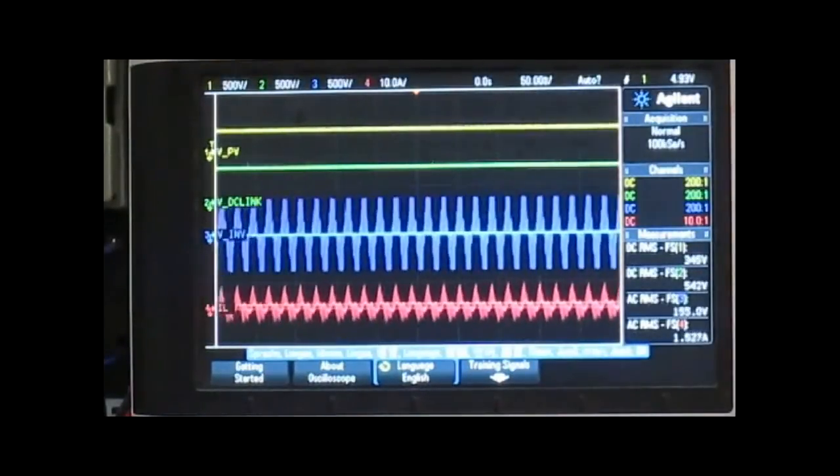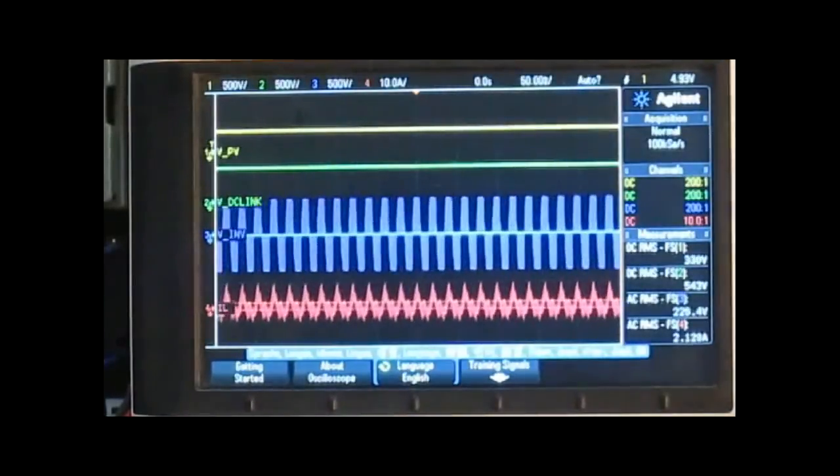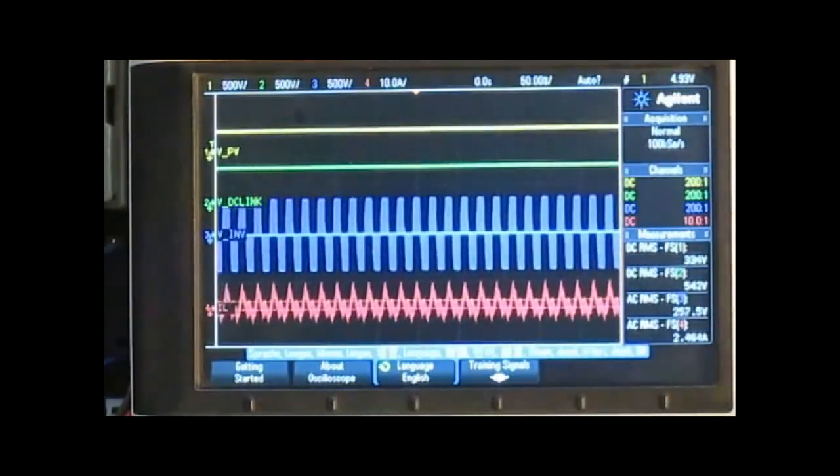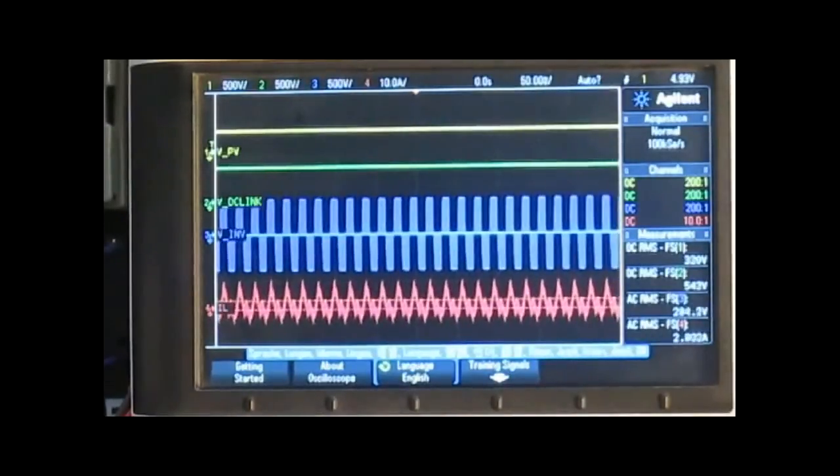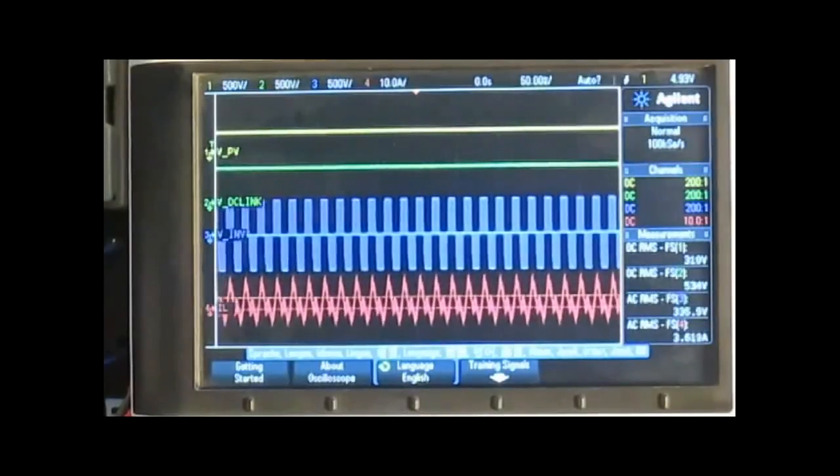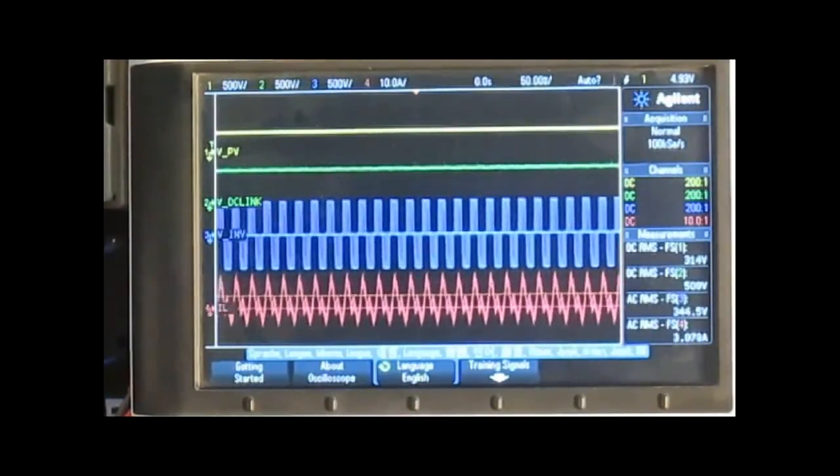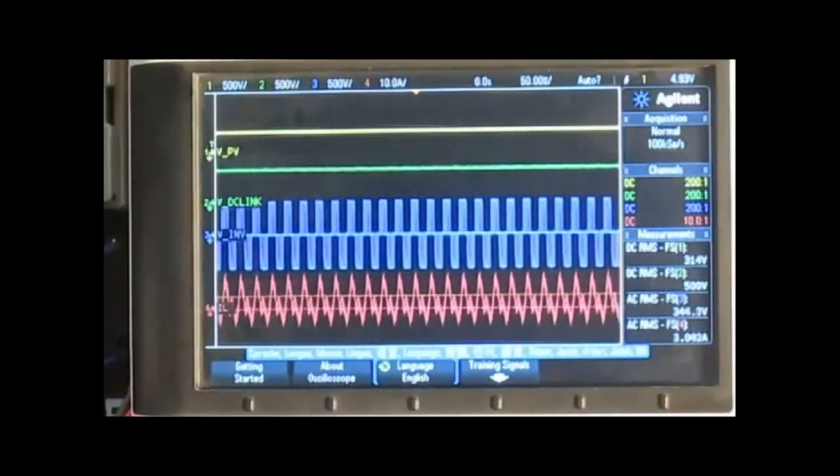Now the 3 MCBs are turned on as explained. Now we can watch the voltage applied to the induction generator which is slowly increasing automatically in a very minute fashion such that there is no inrush current in the induction generator. The blue color waveform is the line-to-line voltage applied to the induction generator.